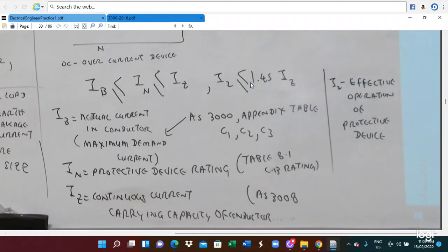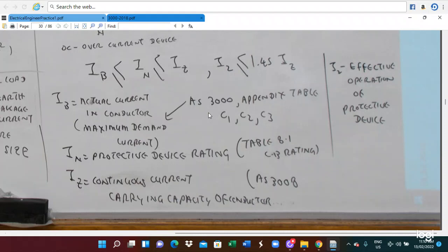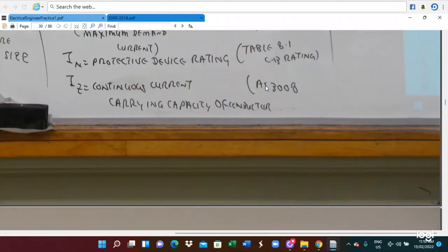In the meantime, another thing is that I2 is less than or equal to 1.45 IZ. I2 is the effective operating current of the protective device, and IZ means the continuous current carrying capacity. So you multiply IZ by 1.45, and I2 must be less than or equal to that. So this is for the effective operation of the protective device. This is the way we have to select the appropriate current rating. So this is the configuration of the electrical circuit.